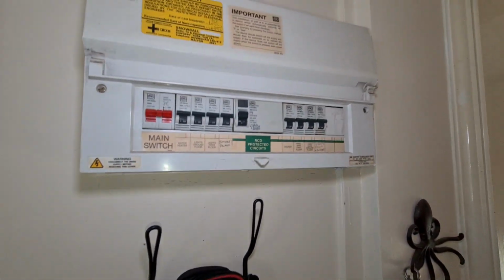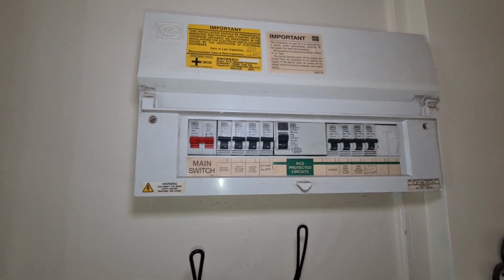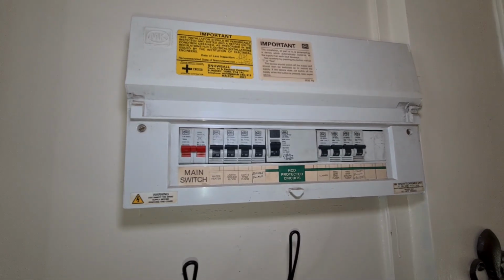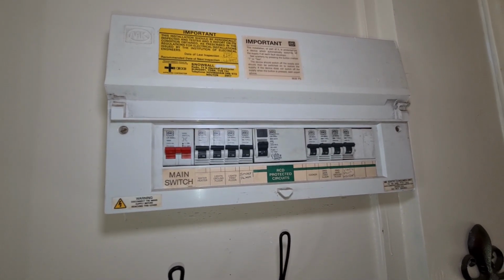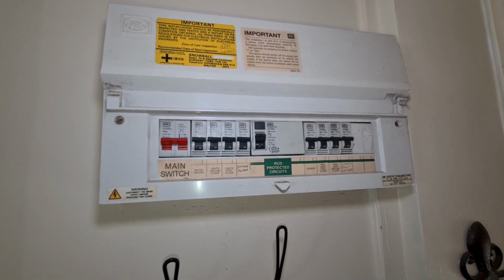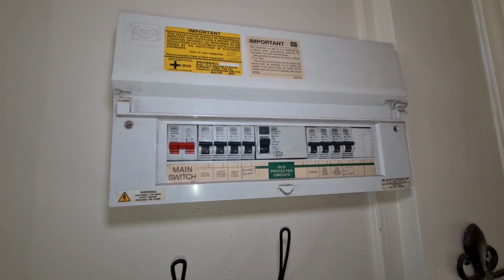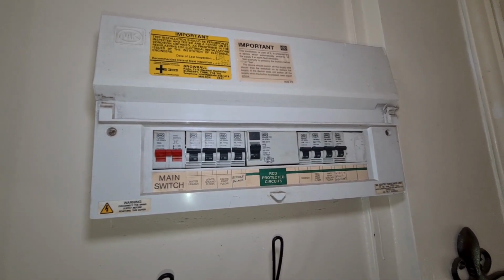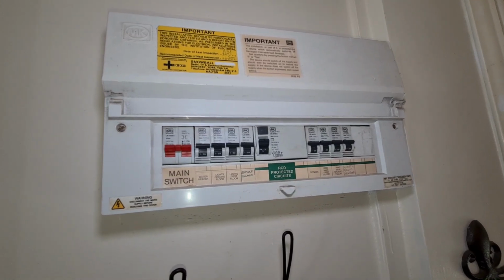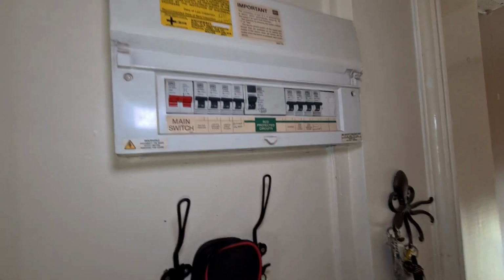However, if you imagine if this was a 3-phase 24-way board on a massive commercial install, and they all need their RCD tests to be done in varying different ways that result in more work, then the time frame for it being done can be increased, and it's a cost to your consumers. So you need to make sure that that cost is justified and it is a test that needs to be done. Otherwise you are charging them for something that's not needed. That's my long and short take on that.